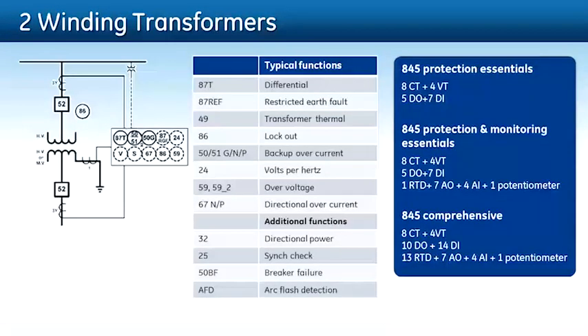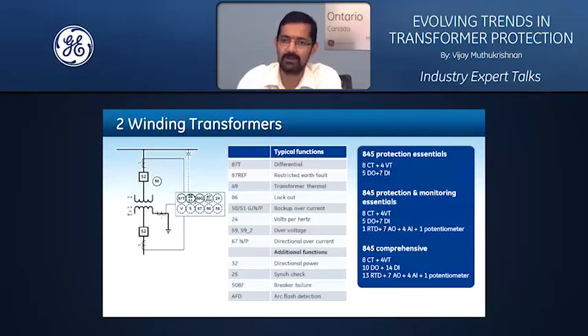In this application scenario, on top of your core differential, restricted ground fault, and overcurrent based functionality, you now have the ability to apply protection functions like volts per hertz, which is a very important function when it comes to transformers to detect overexcitation conditions and overvoltage. There can be transient overvoltages in the system that stress the transformer, so you must be able to identify those conditions and isolate them. Directional overcurrent, in terms of how your system is designed, if you want a directional backup functionality, you can have that. You can use the transformer protection relay for directional power and various other energy metering functionalities. On top of that, you can also use it for synchro check functionality. Say, for instance, you have a generator step-up transformer condition, you can use synchro check functionality in a scenario like that.